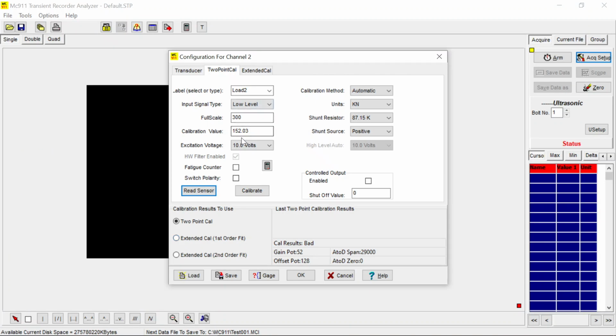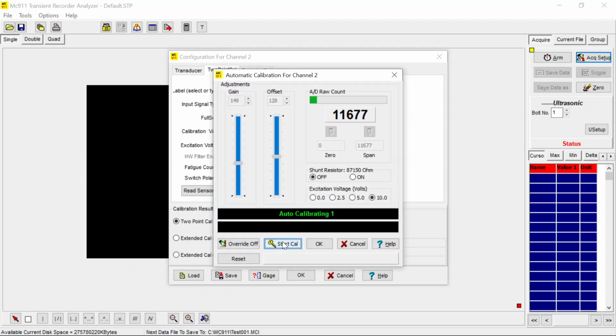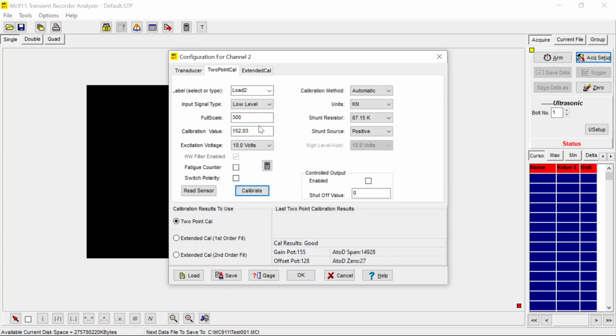So it is calibrated at 152.03 kilonewton and is using the shunt resistor 87.15K. So we calibrate this. The reason we're using this low value, about half of the full scale, is that we can adjust the full scale to anything we want as long as we're above 152 kilonewtons. So our range is 300, so we leave it at 300 kilonewton.